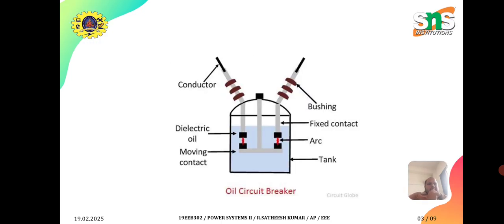This is the diagram of the circuit breaker. You could see the conductors are marked at the top, then bushings. Then there are two contacts, a fixed contact and a moving contact. Those contacts are submerged in the oil. So when the arc occurs, the dielectric oil will suppress the arc. Oil circuit breakers are somewhat bulky in size because of the oil tanks, and periodic maintenance is required because the oil loses its dielectric strength after several reclosing and opening operations of the circuit breaker.